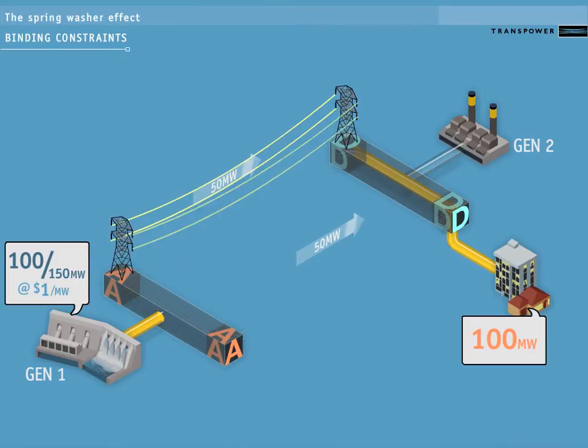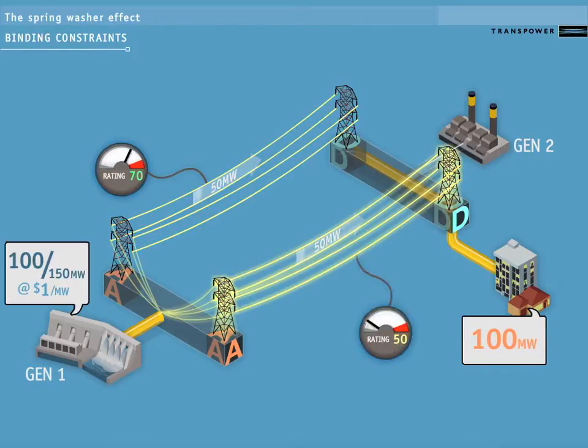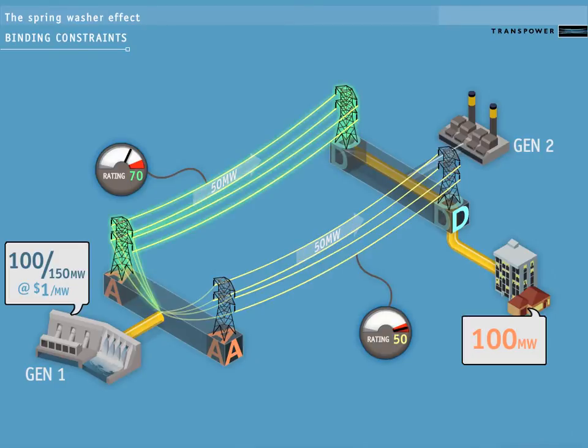Although they have the same impedance, our two transmission lines do not have the same rating. This line has a rating of 70 megawatts, and this line has a rating of only 50. In this case, it has a lower rating because it has less clearance below it. There are many reasons for lines to have different ratings. The higher rating means this transmission line can carry more power than the line with the lower rating.